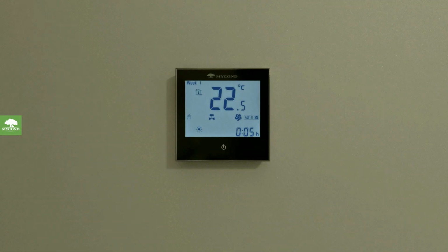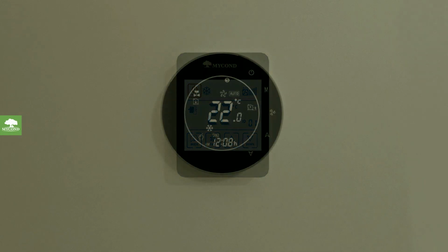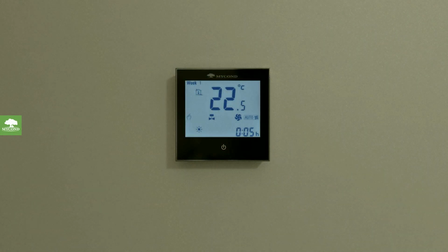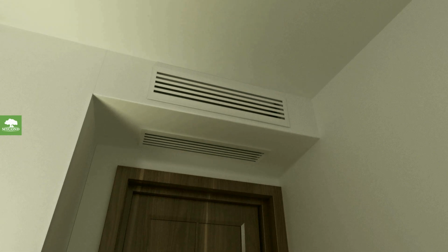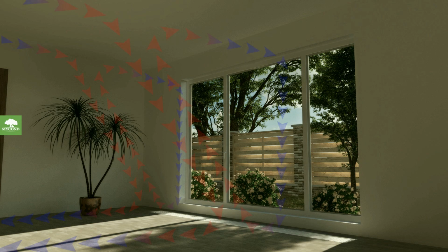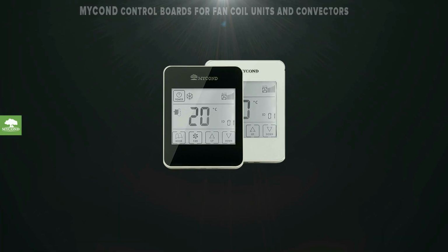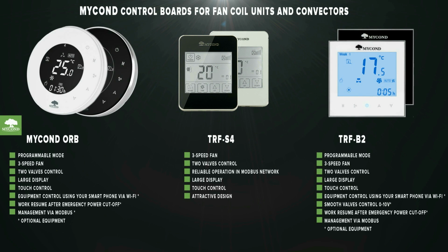You can control the operation of duct fan coils and floor convectors via Mycond control panels. Control device configurations can be set via black or white touch panel. Mycond control panels allow to manage both 2-pipe and 4-pipe fan coils. It is also possible to smoothly control the work of the floor convector inverter fan due to the signal 0-10 volts. These control panels can be connected to the building dispatching system, and their work can be managed from your smartphone using Wi-Fi.